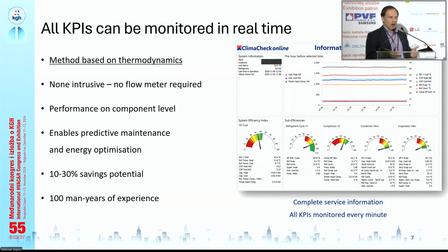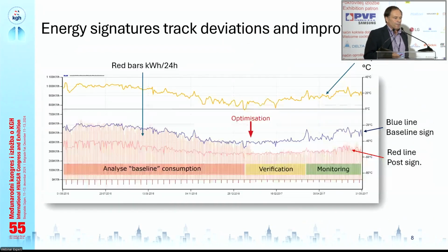And then, as Andy mentioned, energy statistics are extremely interesting. And we let the service calculate an energy signature, because if we look at different outdoor temperatures, we can take the statistics at 10 degrees, 11 degrees, and so on. And this means that we can start benchmarking systems that are in different climate zones. And you can, in each system, see if you make a change, did it improve or did it not improve? And you can also monitor if you deviate from the energy signature that the service built. So then you have all the performance information on component level, and you have the total outcome, including insulation, if somebody closes the door or not, or whatever. So you have both the total outcome, and you can track the changes.